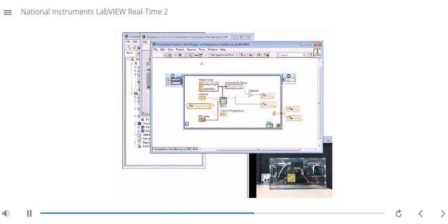Here we have a pretty simple block diagram consisting of a single timed loop and the PID function. Here's a temperature I/O variable that communicates directly with the scan engine on the LabVIEW FPGA target. This I/O variable is passed to the process variable input. The set point, what the user directs us as the desired temperature, that is passed to the set point input. Right now, this is just on the front panel of this RT VI. We'll do more with that later. And of course, we pass in our PID gains as an input to the system.